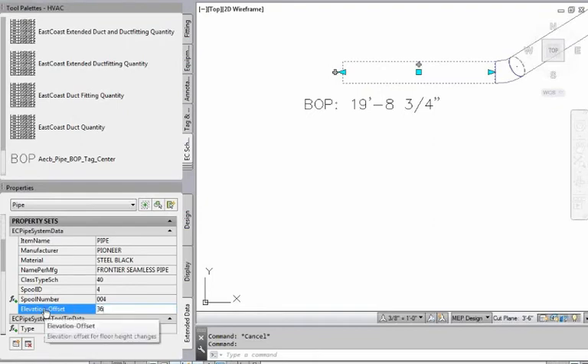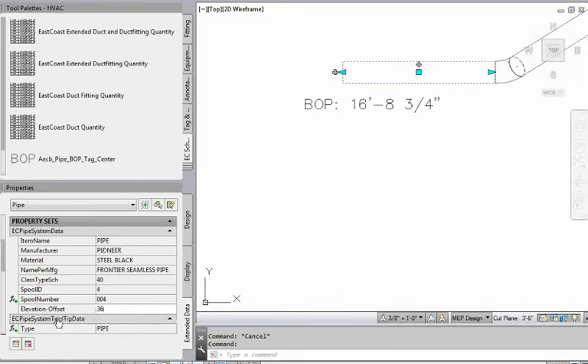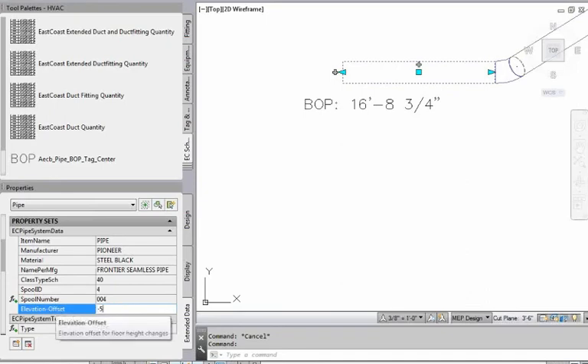And watch the screen as it changes the bottom of pipe. So that took away three feet. So that was like I was going over a raised floor. If I want to deduct it off of here, I can come in here and put a negative five feet. And now we've got 24 feet for that one particular pipe. That only affects that one particular piece of pipe.